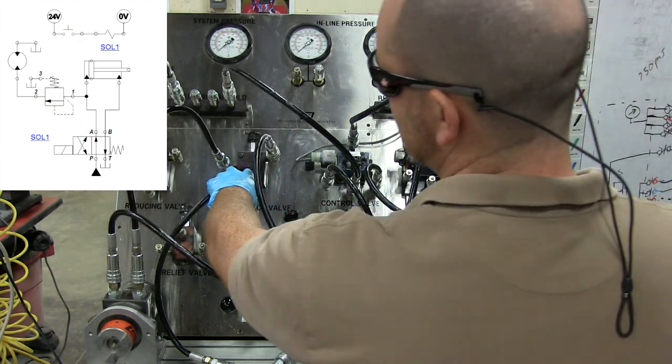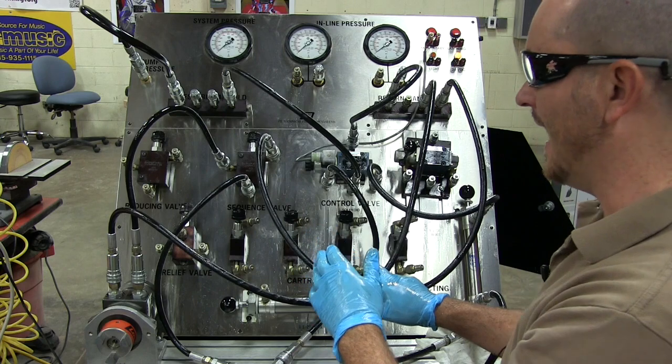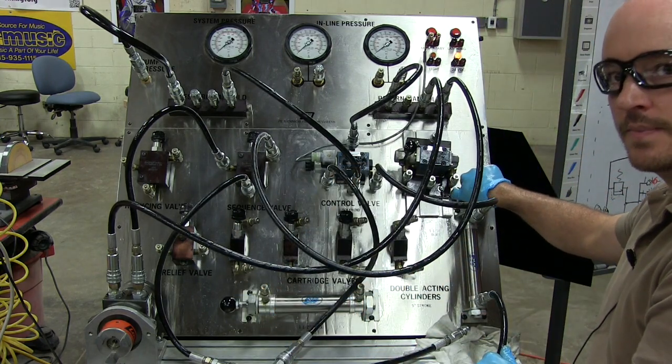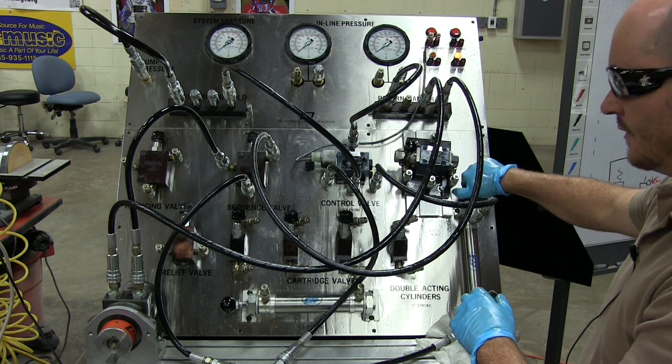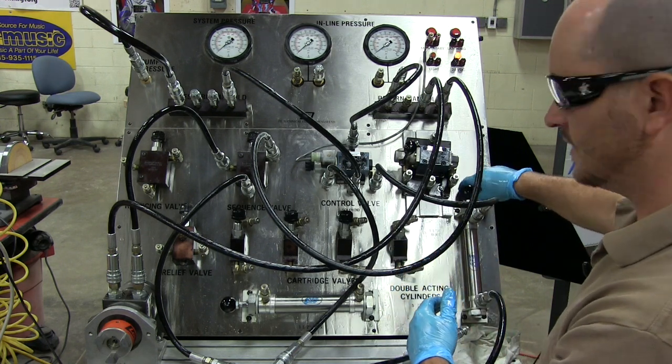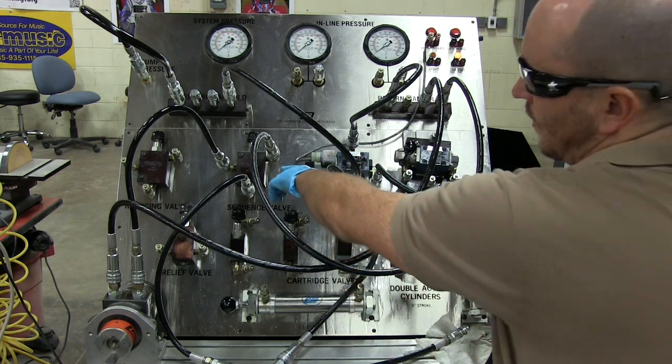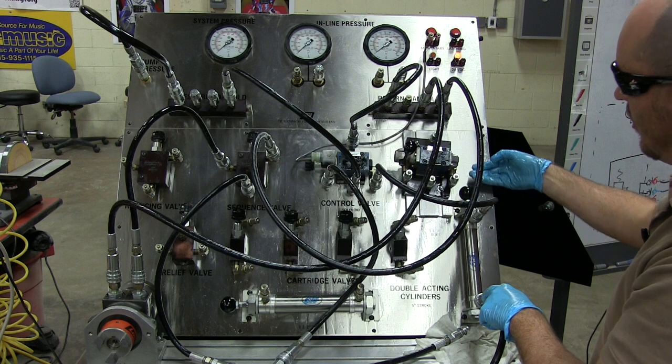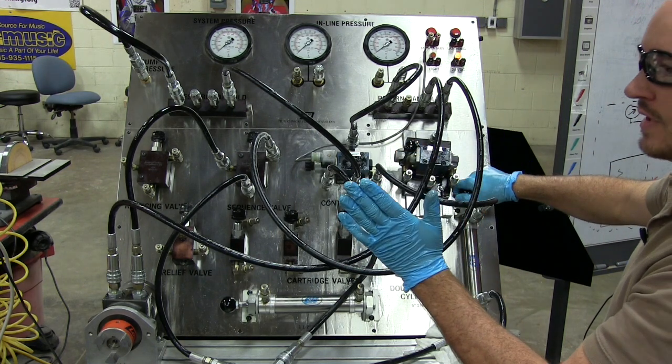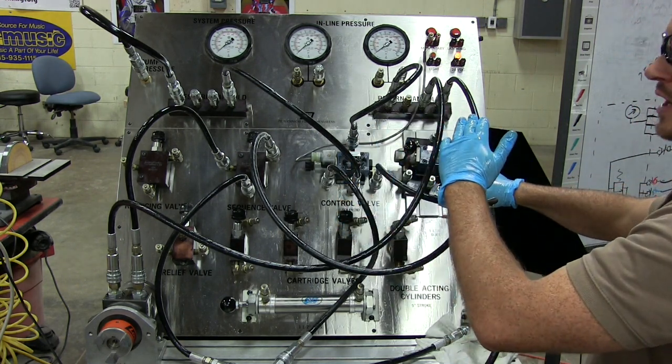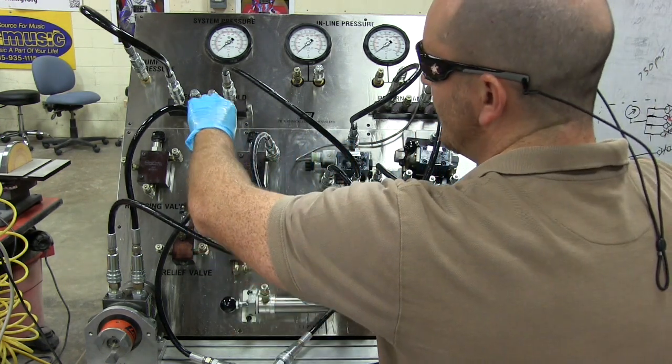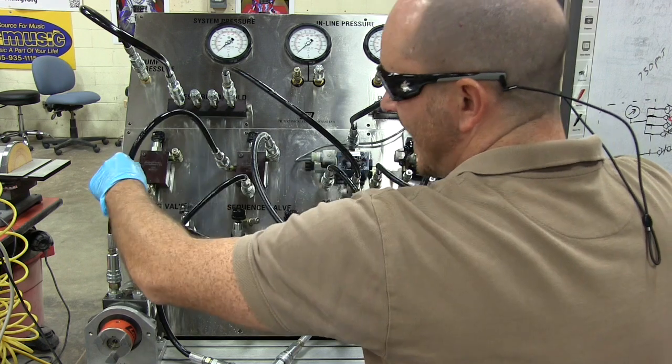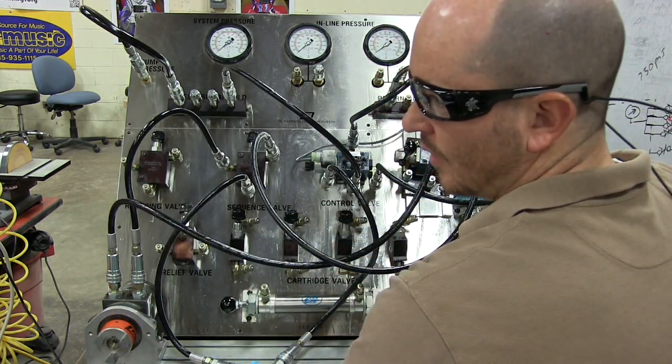Now, this sequence valve is set, I believe, to about 400 psi. Really, in this case, it doesn't matter. There's no load on our cylinder. But if there was a load that required, let's say, 300 psi to extend out, we would want to set this at 400 or 450. So when this extends all the way out, we'll go from 300 up to max pressure. And that max pressure is going to be enough to overcome the biasing spring in here and send that oil right down to the motor.